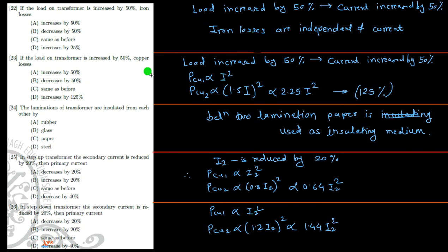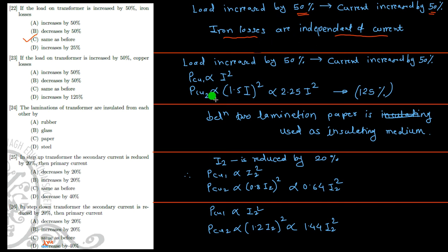If the load on the transformer is increased by 50%, what happens to the iron loss? If the load is increased by 50%, the current is also increased by 50%. But iron losses are independent of current — they depend on the applied voltage. Hence, iron losses will remain the same as before.